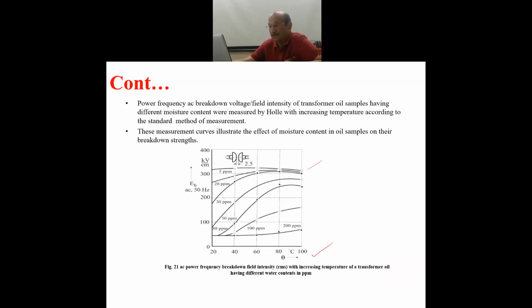That means you take away the humidity content and also the other foreign particles which come up in the transformer because of so many types of electrodes, insulation, and everything being used. There are so many materials. Steel is there, copper is there, so many fibrous materials or maybe pressboards are there. All these may give out some foreign particles, and all these things adversely affect the breakdown strength. So this is an interesting measurement done by Holle.